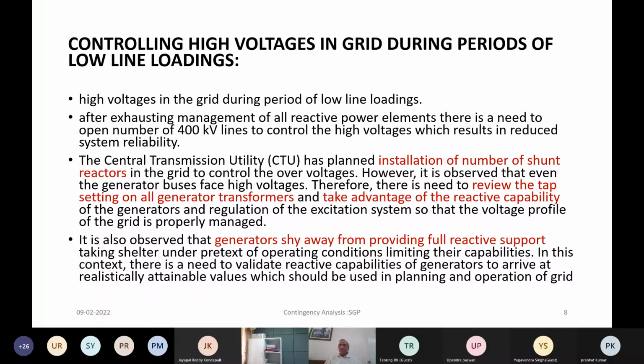So one of the measures is the number of installations of shunt reactors in the grid to control high voltage conditions. Then the tap changing of the transformers, especially the generator transformers, will help. Also, taking advantage of the reactive capability of the generators by controlling the excitation system will have to be more effectively used. So the generator should participate more effectively in voltage control and reactive power support.